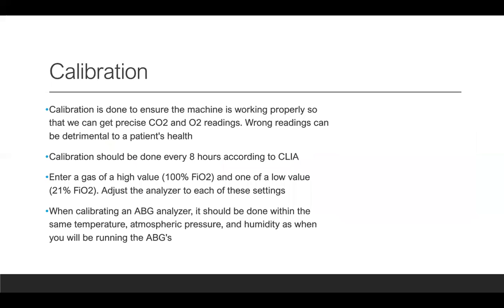And calibration. So I think that this is probably the most important component of an ABG machine. Calibration is done to ensure the machine is working properly so that we can get precise CO2 and O2 readings, and also pH. Wrong readings can be detrimental to a patient's health. So if we're not calibrating correctly and we're not ensuring that we're staying on top of the calibration, our numbers can be off, which will then change our care plan for a patient.